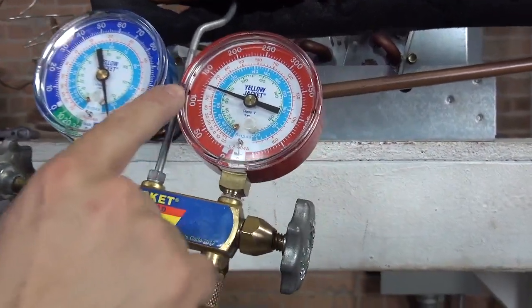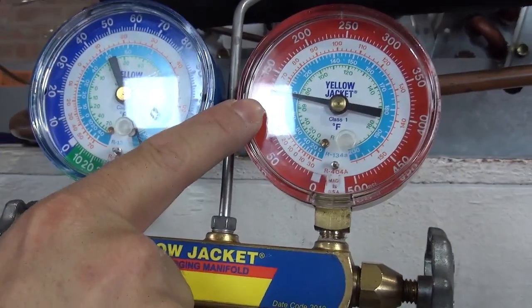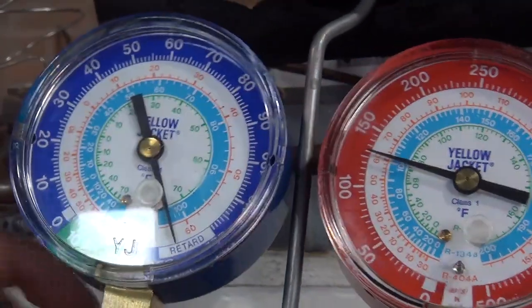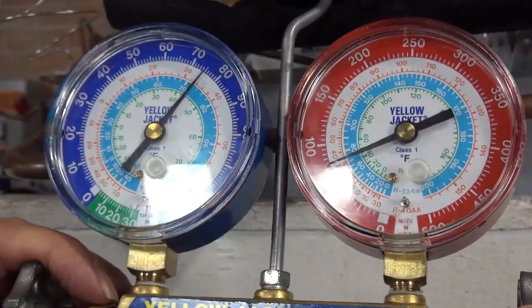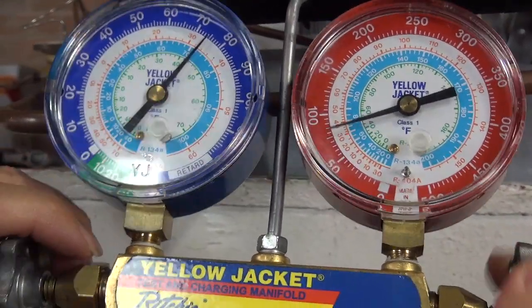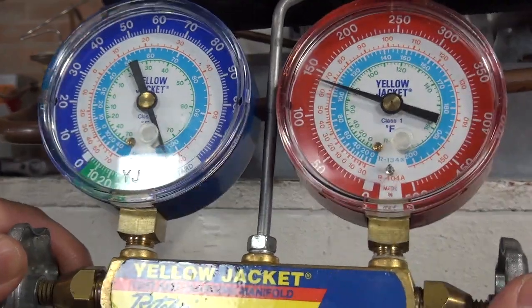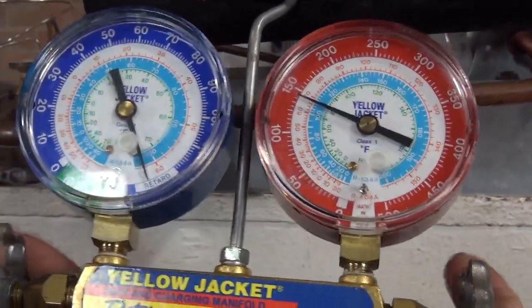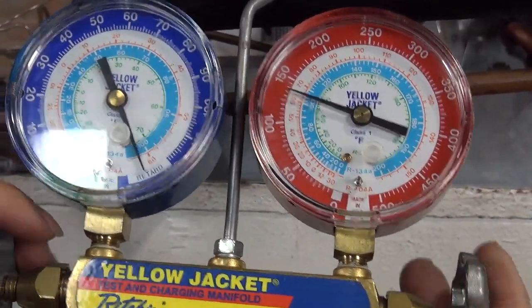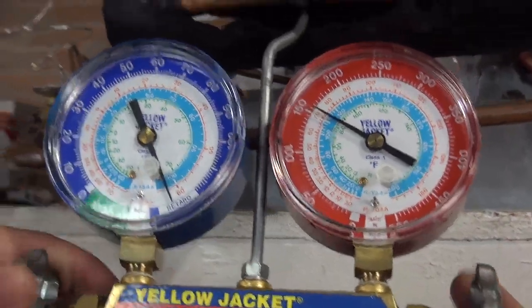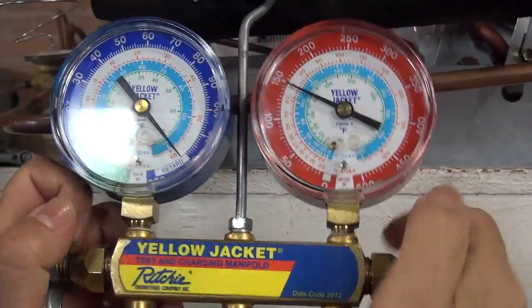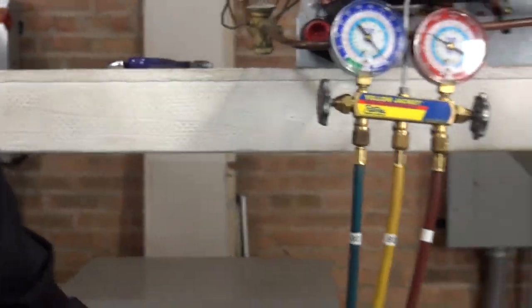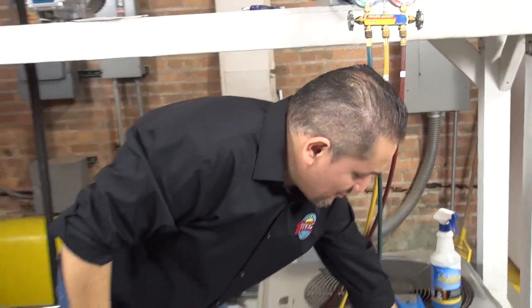Now what you're going to do is monitor. You can actually use the high side to monitor, to make sure the pressure doesn't go more than 150. Sometimes what you can do is just close both of the gauges to see where the pressure is. And it's about 75. We need more. Remember, we need to bring the system all the way to 150. This looks about 150. Close it again. More. Close it again. And right there. You've got to make sure you close the high side, make sure you close the low side. And now, remember, we bring the pressure over to 200.